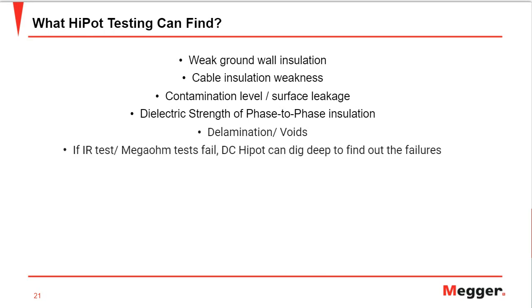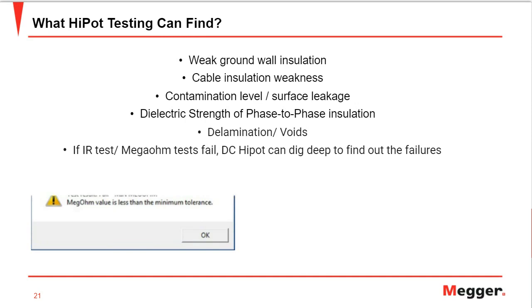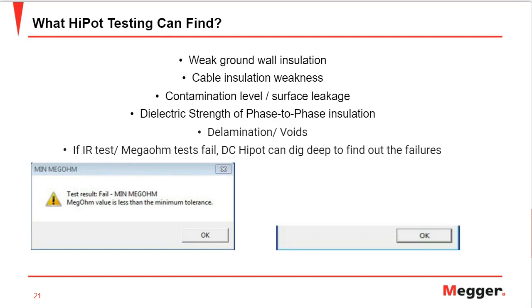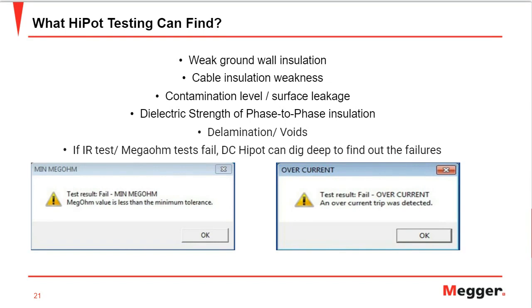If an IR or megohm test fails, which is usually done at the rated voltage of the motor, we can conduct a DC high-pot test to dig out more on what part or what insulation the motor is failing on. Here I have a pop-up message from the software or the tester that the test failed on the megohm test. So we just conduct a DC high-pot test to see what the reason is. And again, we found an overcurrent trip. So that definitely tells us there is some bad insulation on that particular phase.